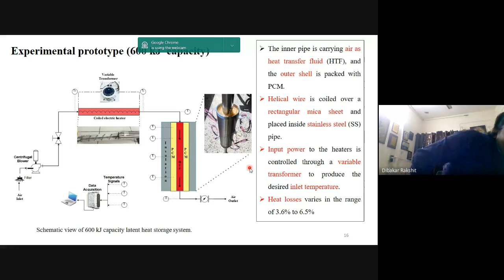Anyways, now we proceeded further. As I told you, we made a prototype thermal battery in our lab at IIT Delhi only. It consisted of an inner pipe, which was utilized to charge or discharge. We had a core and shell type of arrangement. The tube, which was the core, had hot air being blown through it, and then we had the outer structure, or the shell, where we were packing all the phase change material which we wanted to melt, and to see how the strength of the charging and discharging of that phase change material performs.